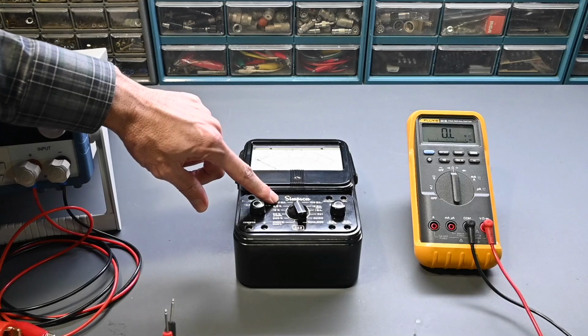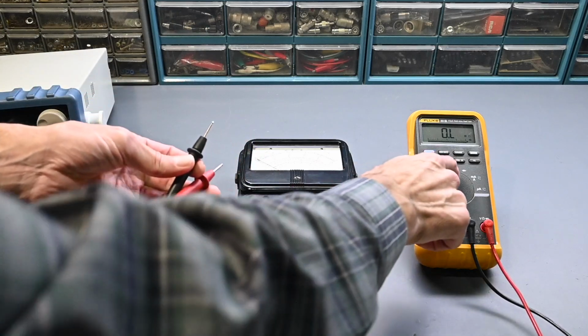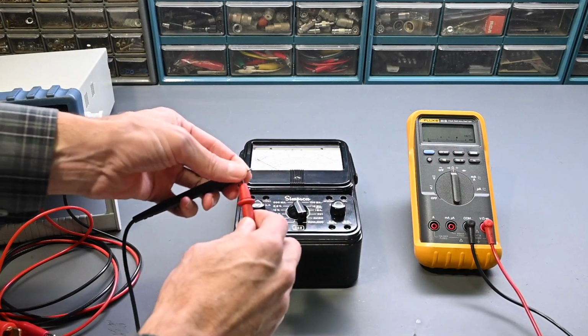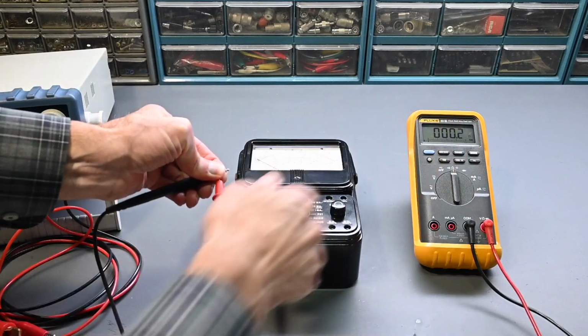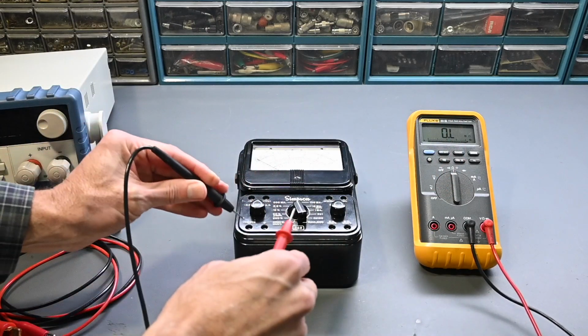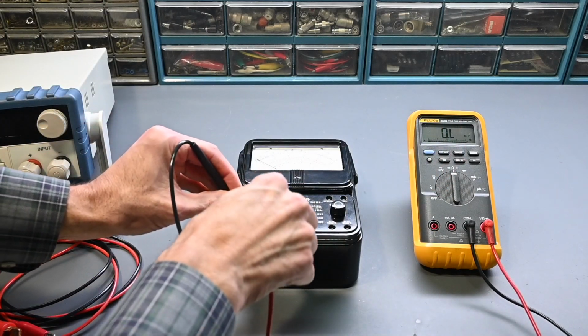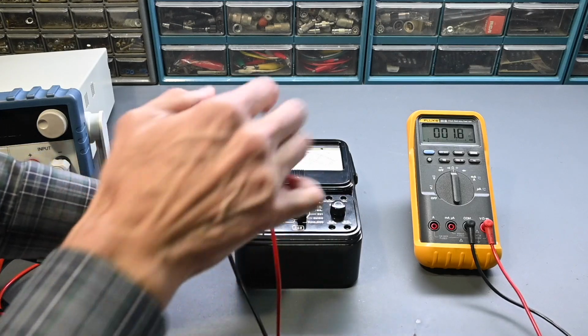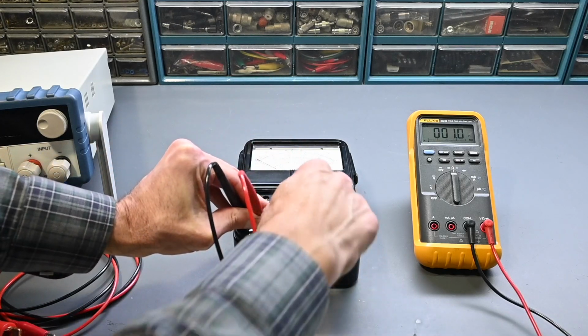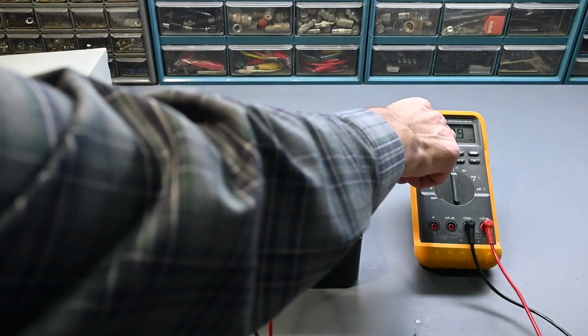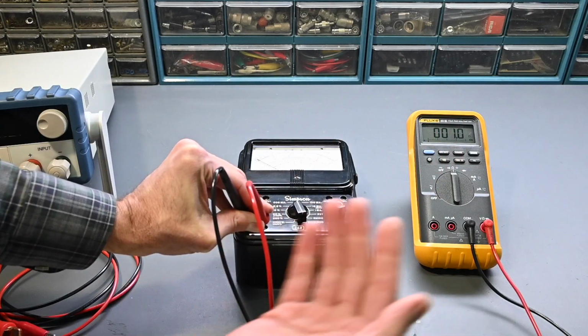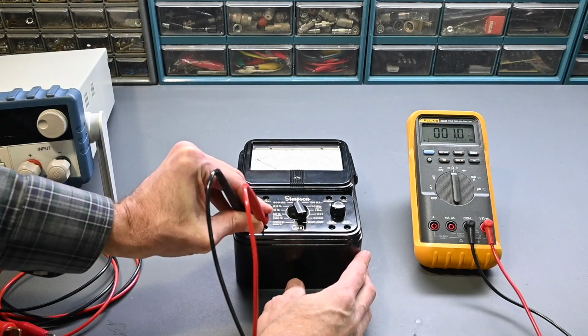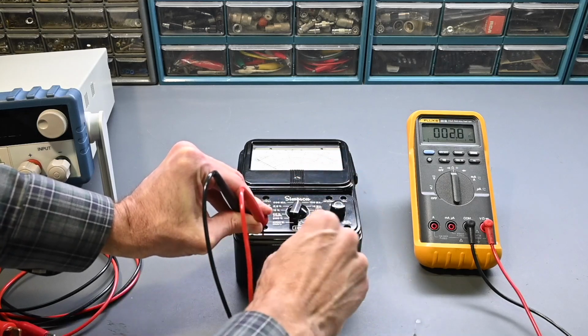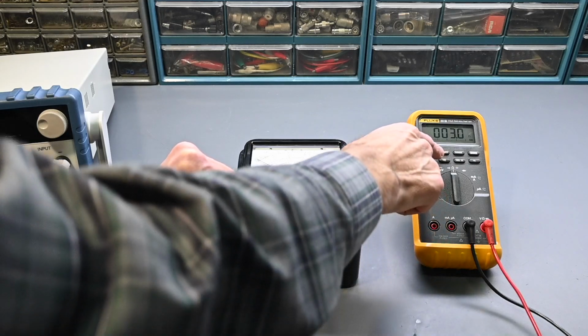So it's set to 500 milliamps right now. So of course this is, again, on the resistance setting. If I touch the probes together, it falls down to a very low value. So I'm just going to probe in here to the jacks on the front panel right there. As you can see on 500 milliamps, it's measuring 1 ohm, right? So that's the internal shunt resistance on the Simpson 260. Now if I go to 100 milliamps, now it's 3 ohms.